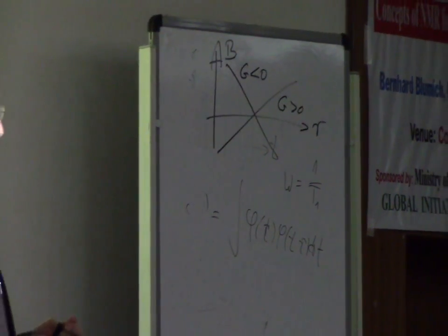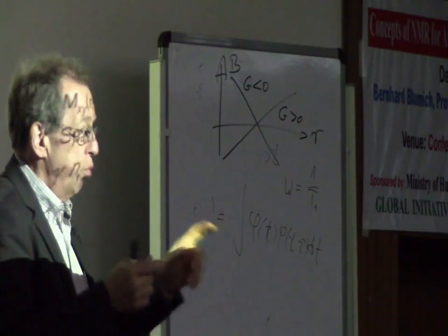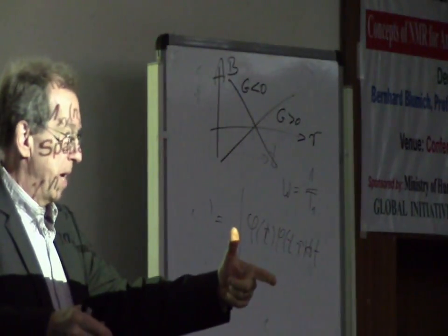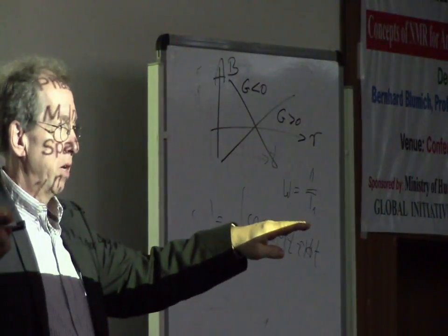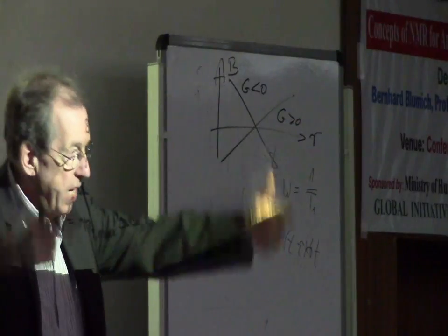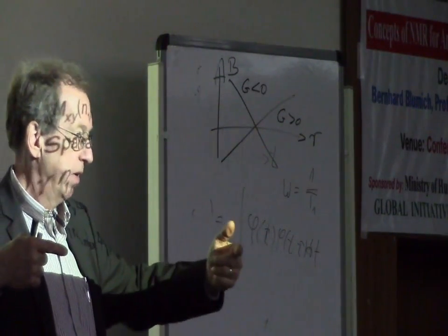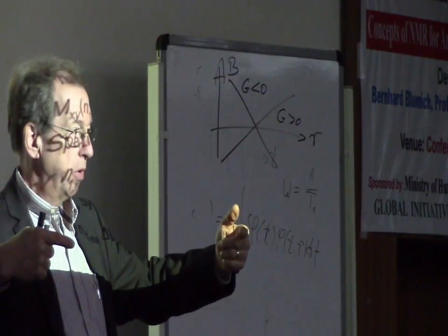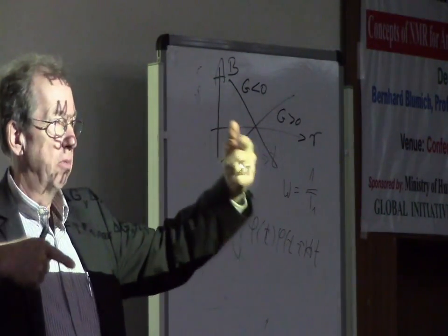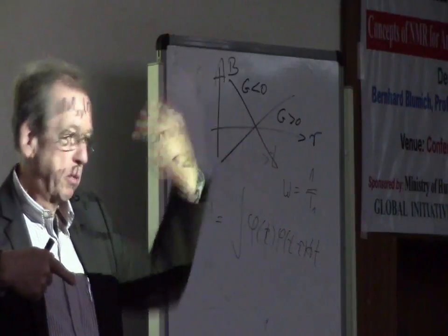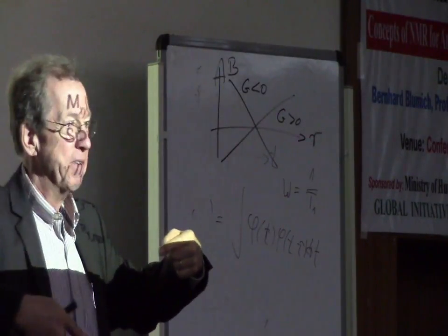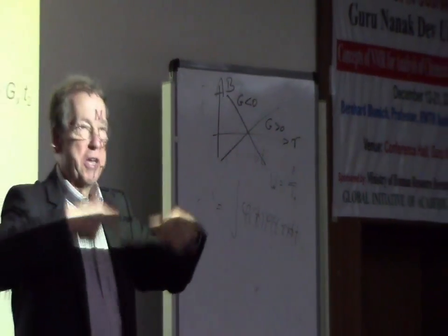There are two fields, right? The field of the superconducting magnet gives you the homogeneous magnetic field, and to this you add a magnetic field with coils that are driven by electrical currents. One current this way, the other current this way. In series I can do it, but you do that in parallel, right?